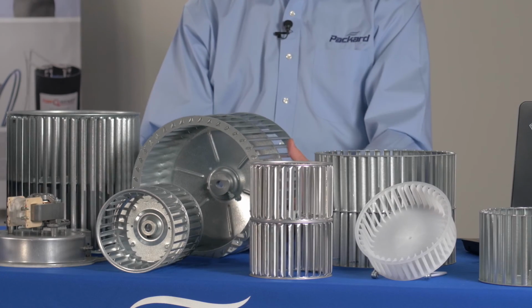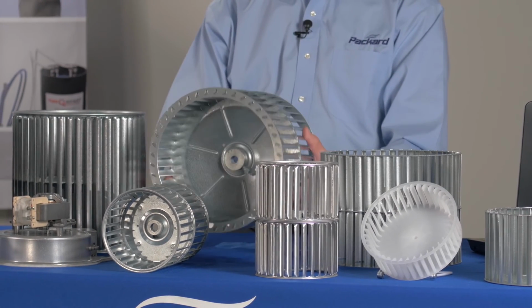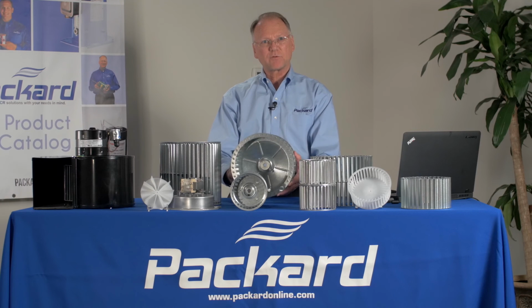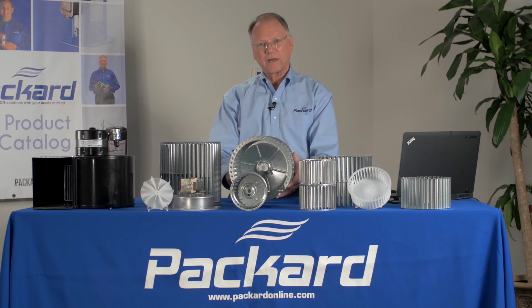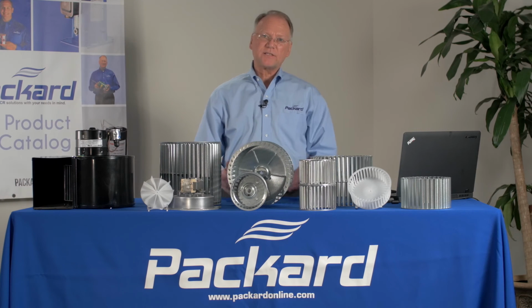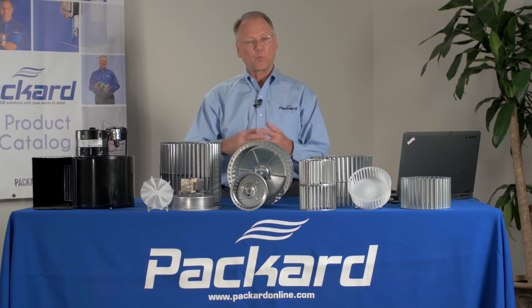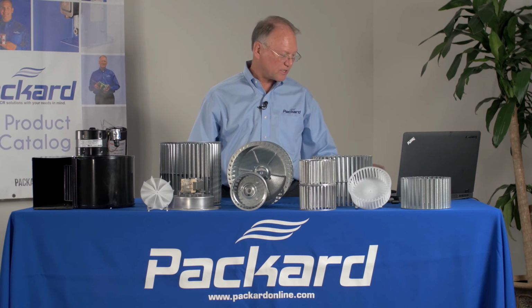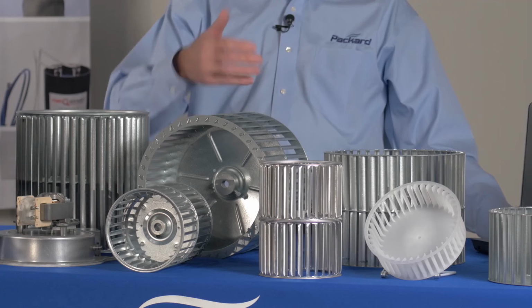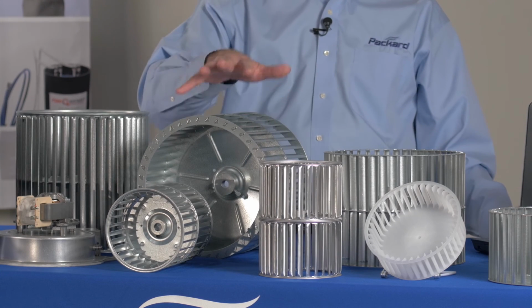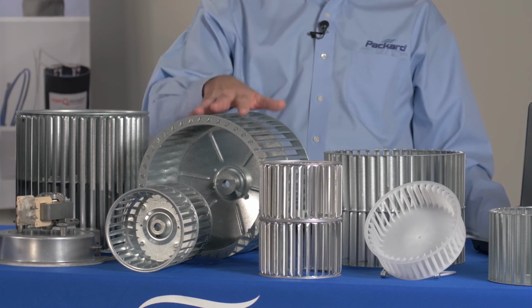The wheels are designed to operate at given RPMs. There are maximum levels of speed that the wheel can operate at. If it exceeds that speed, it's possible that the wheel could come apart and cause damage in the system. So when selecting the wheels, make certain that the wheel is able to take the speed that the motor is rated at.